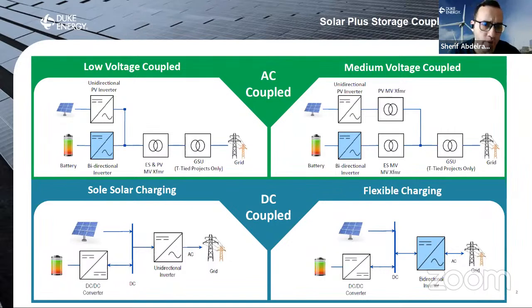Now for low voltage coupled systems, this is an architecture offered by some inverter manufacturers out there, where they basically put 2 inverters on a common skid, and both of them are connected to the same medium voltage transformer. That way, when you're charging from solar directly, you're not going through the medium voltage transformer, both on the charging side and the discharging side. This is a differentiator from the medium voltage coupled architecture.